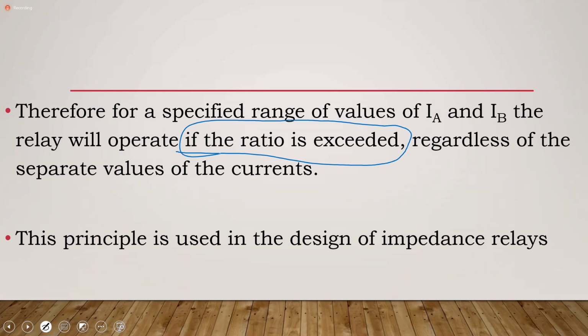Of course, the mere fact that I mentioned that, what is it saying to us? Impedance is what? Voltage over current. Yes, sir. So it gives both current and voltage in its operation. Exactly. So an impedance relay would be like a 21 relay. It sounds like you have some previous knowledge. Yes, that's a 21. That's an impedance relay. It will have a voltage, a VT input, and a CT input. And it looks at these two, compares them, and once the ratio is below a certain value, it operates. Because the comparison that it makes, if you have a specified voltage over current, will give you a specific value of impedance.